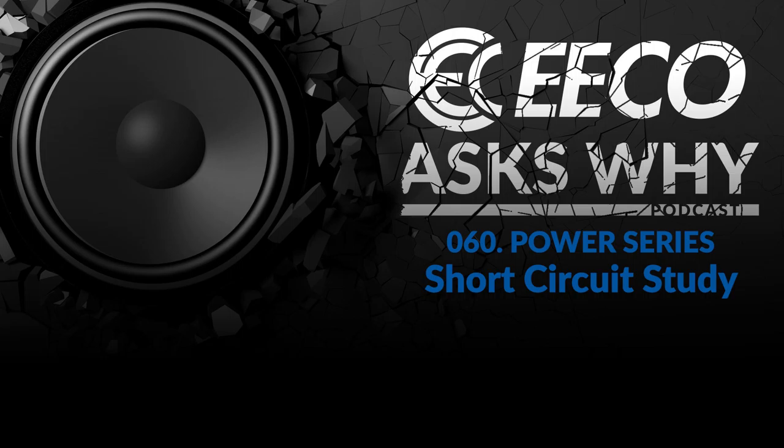Now, bear in mind that a protective device is a static device. That 14 KA is what it was manufactured at. It is not dynamic. It does not change. Even though the short circuit values are dynamic, the available fault current into a system is dynamic.